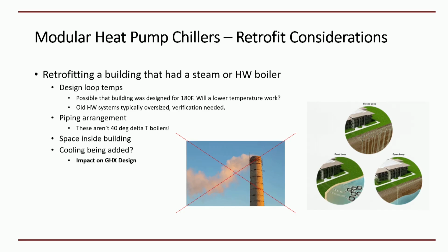Retrofits. This is very common, probably comes up much more commonly than new builds, especially in Western New York. We love our old buildings, and they've got to keep that way, and we have to work within those confines to really make things work. So you might be replacing a system that was a 180 degree hot water loop. Do you need that temperature? This is where we come back to modeling and really doing your homework. Just because it was there doesn't mean it was right.